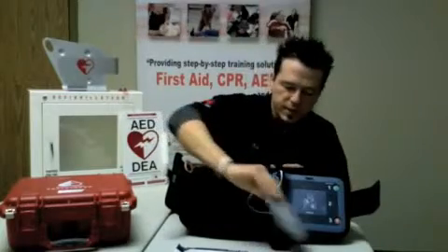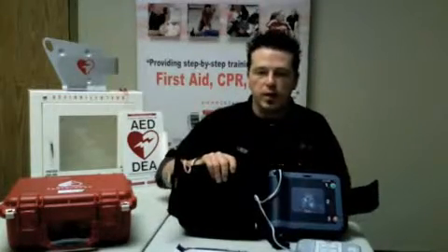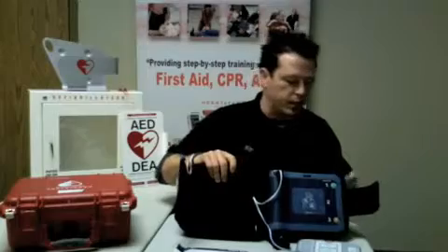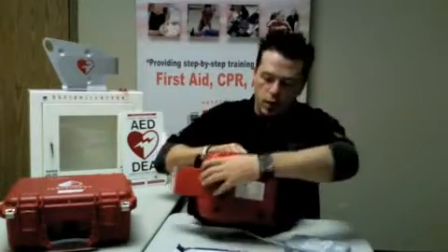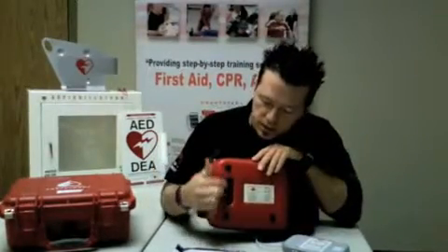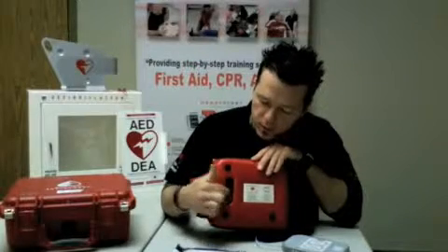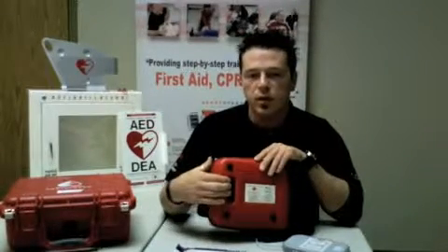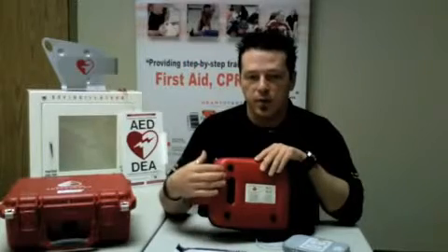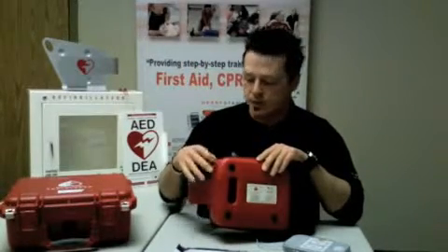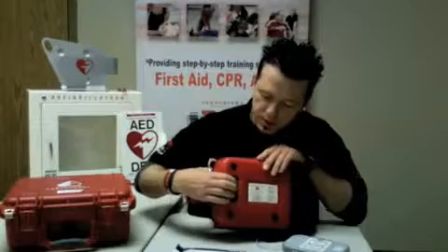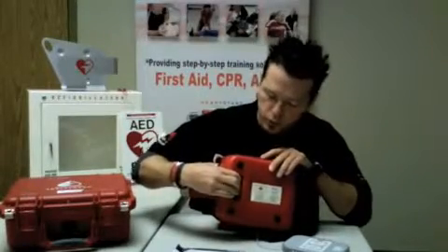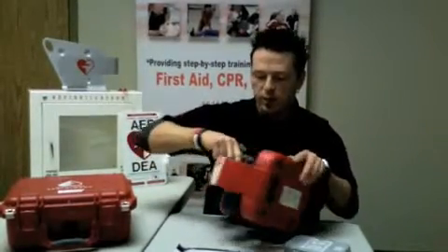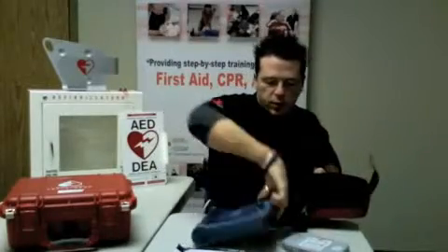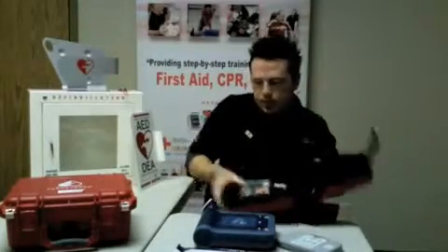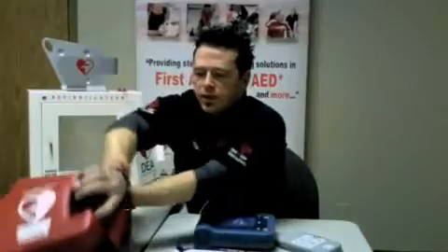I will remove this. And to remove the defibrillator so that we can do the diagnostic test and servicing, go to the back of the case, and you'll notice a black strip of soft material. This is the only way that you'll be able to take out the defibrillator because it's suctioned into the case. By pushing on this material, the defibrillator pops out, and as you can see, it does so fairly easily. Putting this over to the side over here.